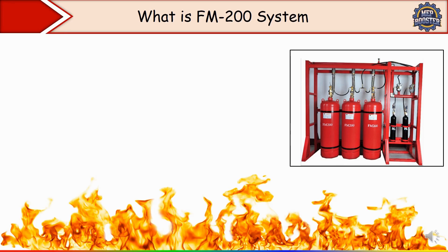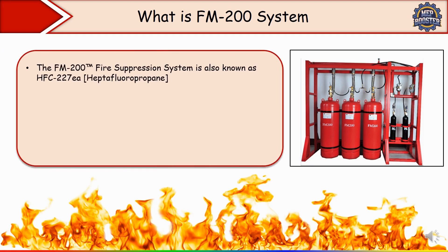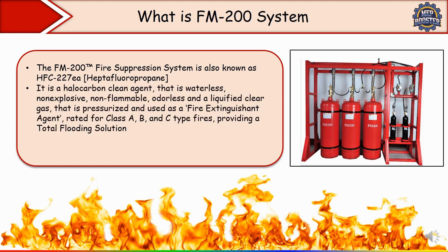First, we'll see what is the FM-200 fire suppression system. FM-200 is a type of clean agent fire suppression system that uses HFC-227EA — heptafluoropropane — as its extinguishing agent. It is a halocarbon clean agent that is waterless, non-explosive, non-flammable, odorless, and a liquefied clear gas that is pressurized and used as a fire extinguishing agent rated for Class A, B, and C type fires, providing a total flooding solution.